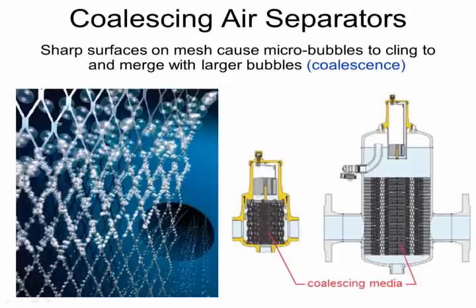Well, here's the inside of a separator. Inside is a coalescing mesh, basically sharp edges. As microbubbles come out of your pipe as a result of heating the water or undergoing a pressure drop, those microbubbles, before they have a chance to go back into solution, attach to the sharp edges. More microbubbles collide with those microbubbles, creating bigger microbubbles. They continue to cling onto the mesh at another point. Eventually, the buoyancy force causes the bubbles to go up into the air vent portion of the separator and vent out, per the process we saw a few slides ago. Okay? That's how coalescing works. Very effective at taking air and getting rid of it in a system.